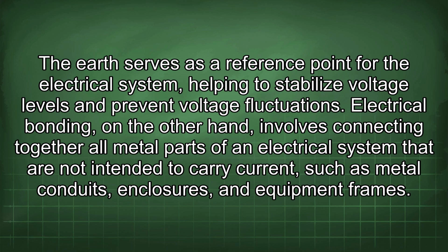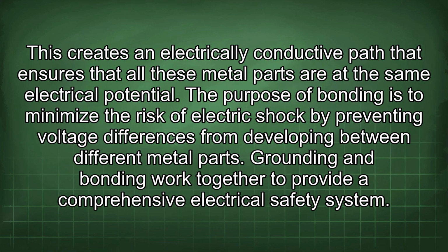Electrical bonding, on the other hand, involves connecting together all metal parts of an electrical system that are not intended to carry current, such as metal conduits, enclosures, and equipment frames. This creates an electrically conductive path that ensures that all these metal parts are at the same electrical potential. The purpose of bonding is to minimize the risk of electric shock by preventing voltage differences from developing between different metal parts. Grounding and bonding work together to provide a comprehensive electrical safety system.